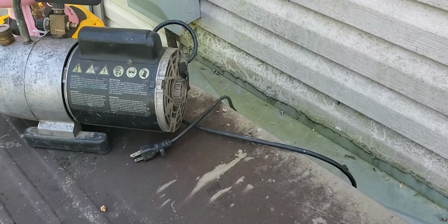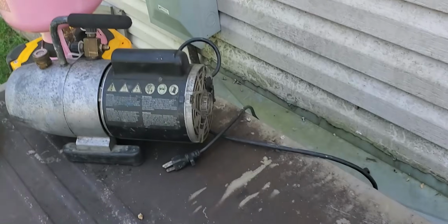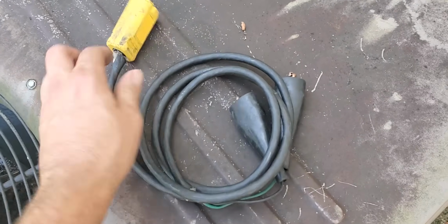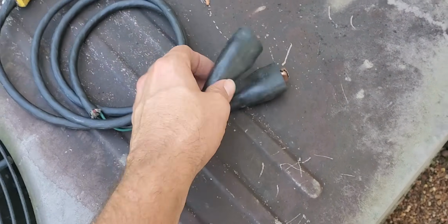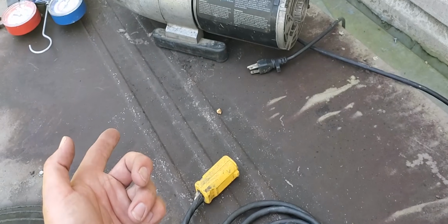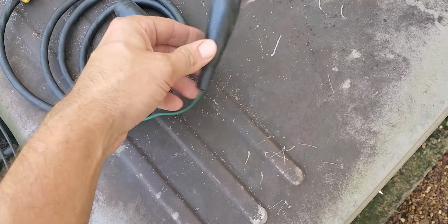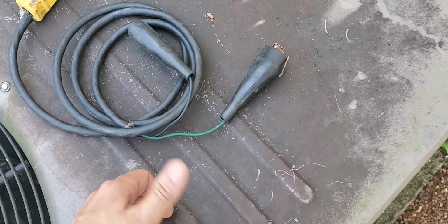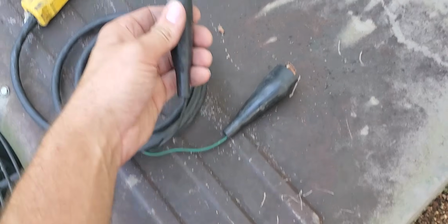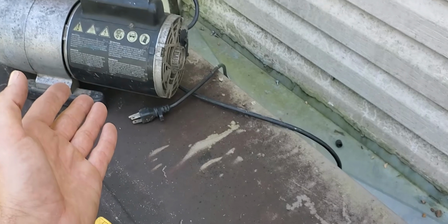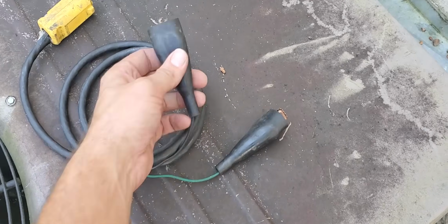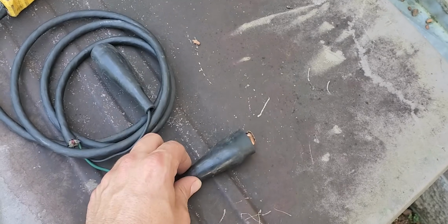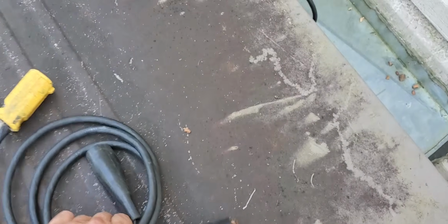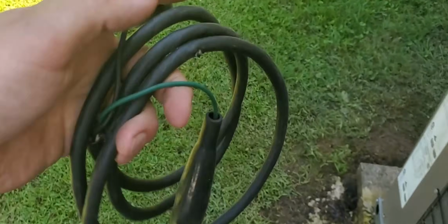If you can't find a plug, a receptacle with power on site, make a cord so that you can pull power. Whether you're taking that power from the equipment in there, some of the electrical components like just the line voltage coming in, there's some terminals you could probably put this side on. Remember, 115 volt pump, it's only going to need one leg of 230 and then the other would go to ground, okay? So if you wanted to make a cord, make a cord.